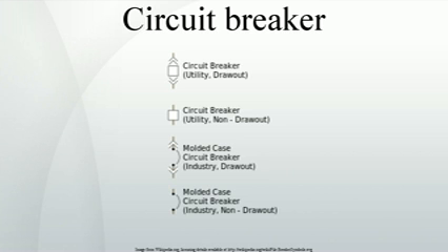Carbon dioxide, CO2, high-voltage circuit breakers. In 2012 ABB presented a 72.5 kV high-voltage breaker that uses carbon dioxide as the medium to extinguish the arc. The carbon dioxide breaker works on the same principles as an SF6 breaker and can also be produced as a disconnecting circuit breaker. By switching from SF6 to CO2, it is possible to reduce the CO2 emissions by 10 tons during the product's life cycle.